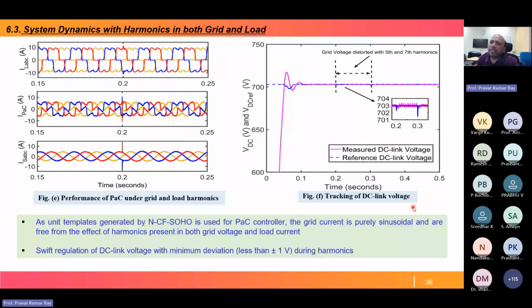Same way for this load, which is also highly disturbed with a highly harmonic component. These are the injected signals, so now it becomes sinusoidal after injecting this signal. This is regarding maintenance of DC link voltage, almost smoothly maintained. If you zoom in the figure, the disturbances are very small, maybe 1 or 2 volts maximum.